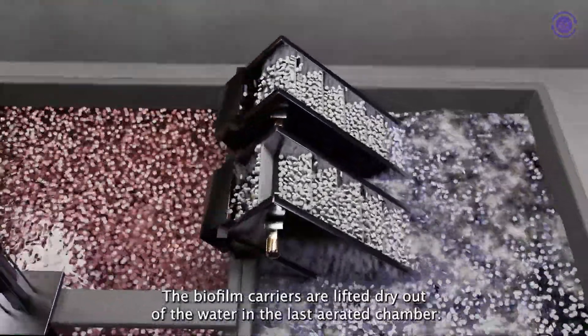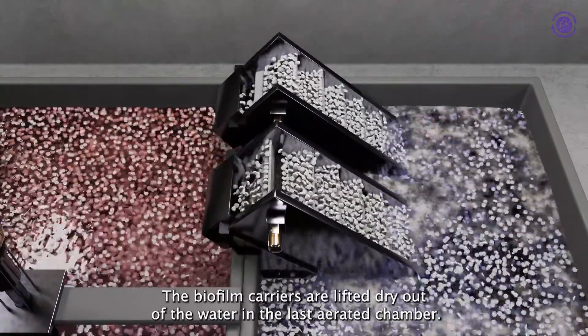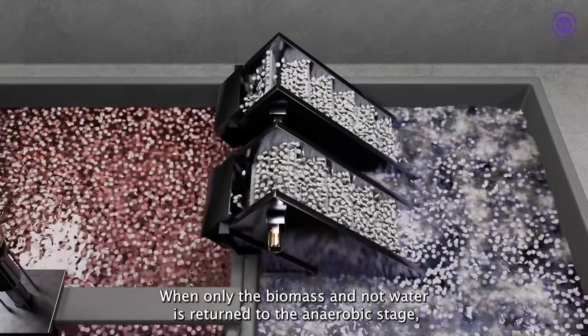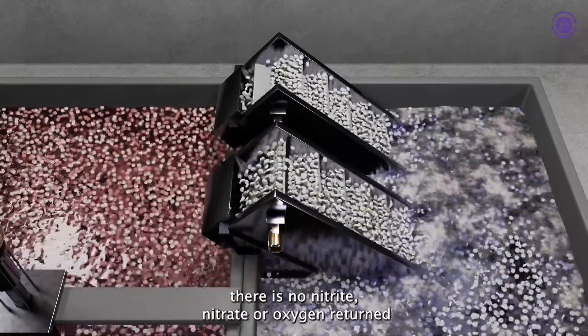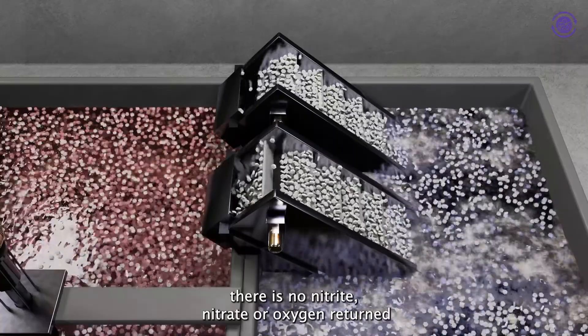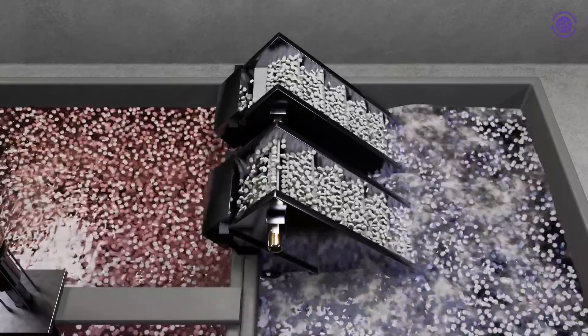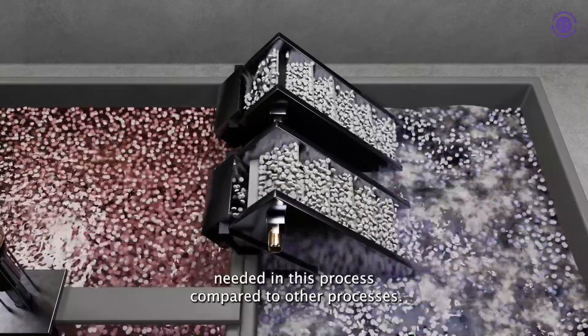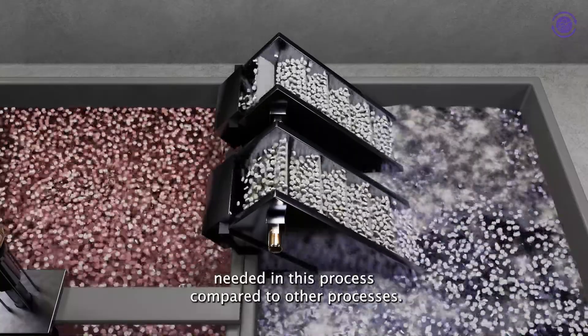The biofilm carriers are lifted dry out of the water in the last aerated chamber. When only the biomass and not water is returned to the anaerobic stage, there is no nitrite, nitrate, or oxygen returned that would have reduced the performance of the biology. This is also beneficial for the hydraulic retention time needed in this process compared to other processes.